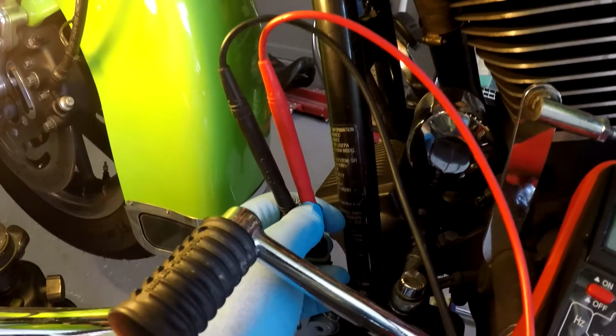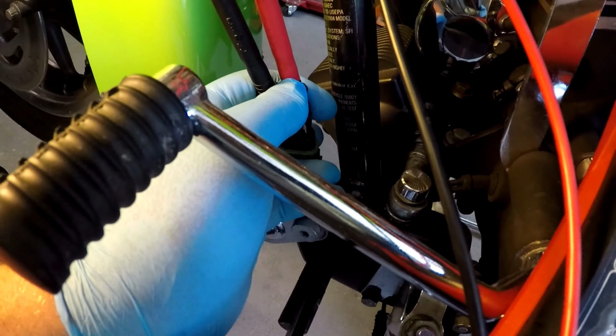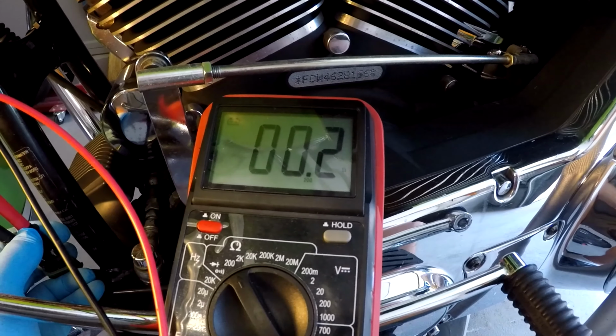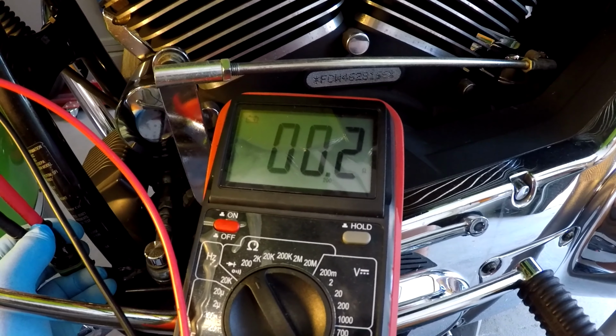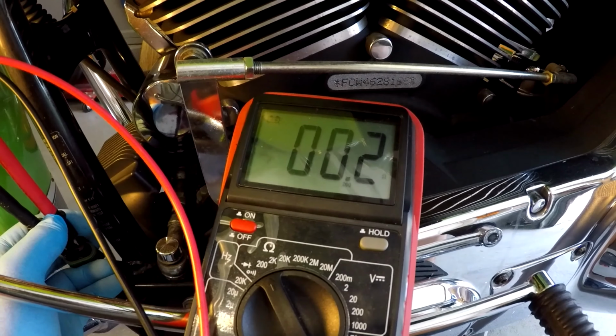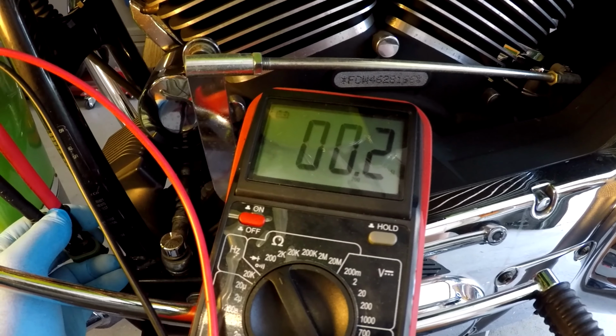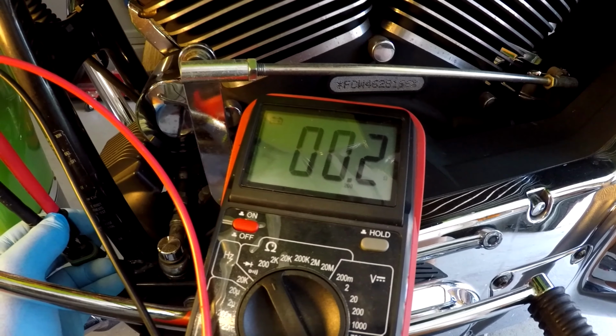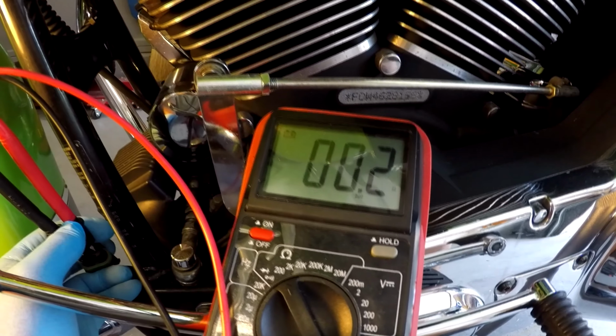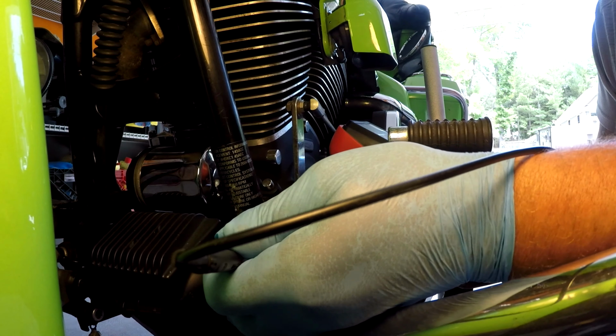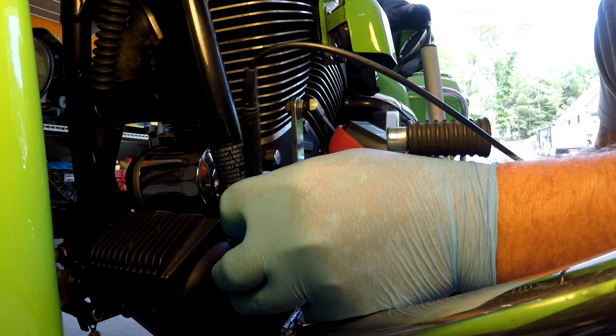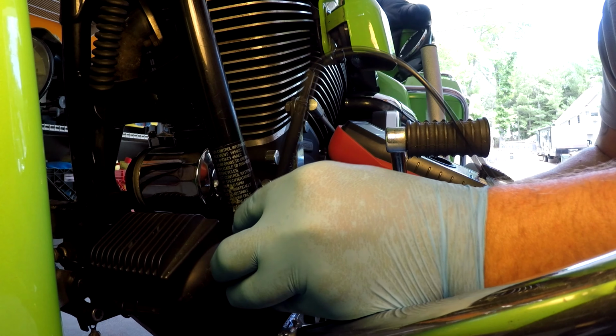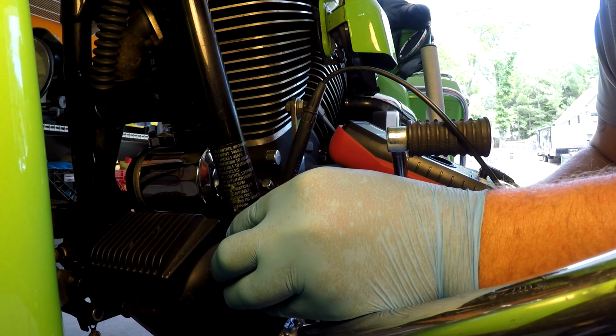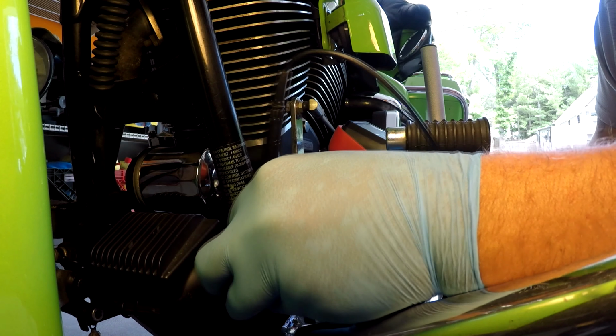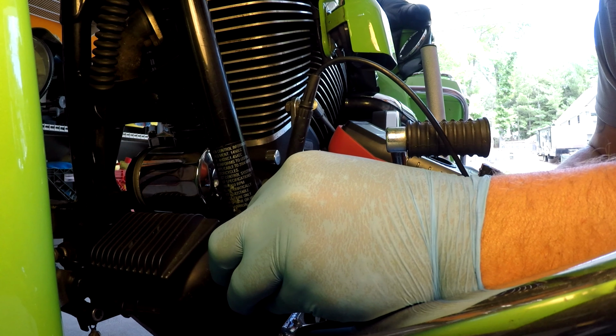Alright, so we got both pins into the plug. We're doing an ohms test, and I got 0.2. Anything 0.5 or over means you need a new stator. Alright, now we're going to check to see if the stator is grounded. To check the stator to see if it's grounded out, you put one probe on one pin, and you put the other probe on a bolt on the primary. And that's good. There's no changes.